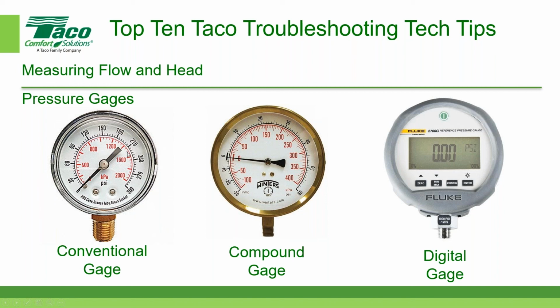So I asked him to remove that conventional gauge and install a compound gauge. And sure enough, when he put the compound gauge in, the dial went down to, I think, about minus 15 inches of mercury. So we were able to figure out that the pressure on the suction side of the pump was much lower than zero, and that was causing the pump to cavitate. So that was another issue. Especially on low pressure suction sides of the pump, it's best to put in a compound gauge rather than a conventional gauge because it gives you a much better reading.